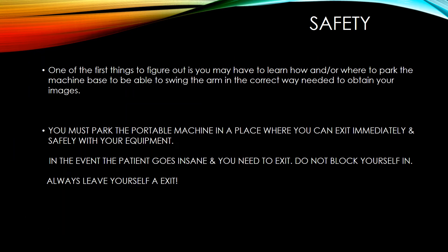Safety: one of the first things to figure out is how and where to park the machine base to be able to swing the arm in the correct way to obtain your images. You must park the portable machine in a place where you can exit immediately and safely with your equipment in the event the patient becomes unstable. Do not block yourself in — always leave yourself an exit.